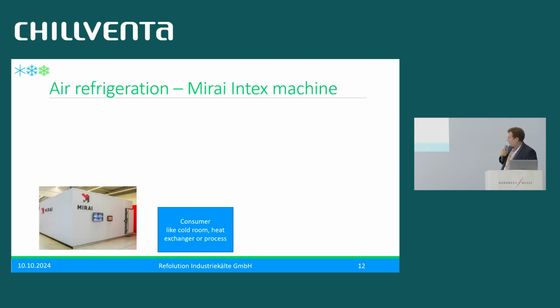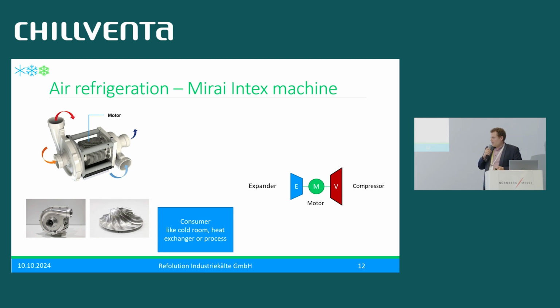So how is it really working? We use this wonderful machine from Mirai Intex. It's produced in Czech Republic. It's a turbo compressor with a turbo expander on one shaft, and the motor is in the middle. So basically, it's a flying machine, speed controlled. It has no liquid refrigerant. It has no oil. It has no vibration. Those of you that know about refrigeration, the main failures of refrigeration equipment are liquid refrigerant, oil, and vibration. Pretty cool, isn't it?